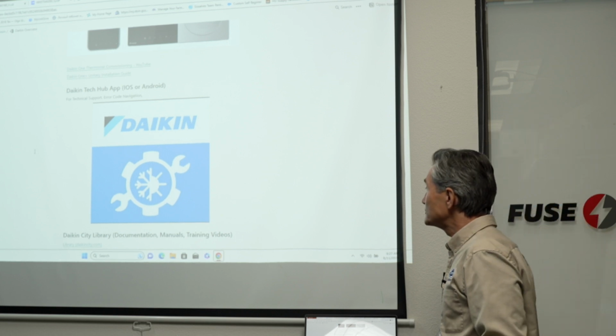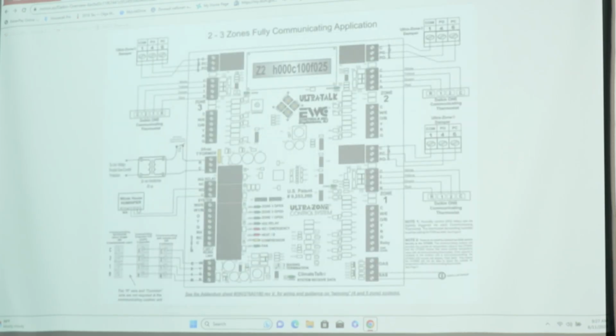Okay, so this is the zoning system for the Daikin. On the left side you can see the communication zoning board. To connect or install zones to the Daikin, this is the only compatible zoning board - we cannot use Honeywell, Aprilaire, or anything else. Only this one works with the Daikin. It requires a separate transformer - it's mandatory, we have to use one.